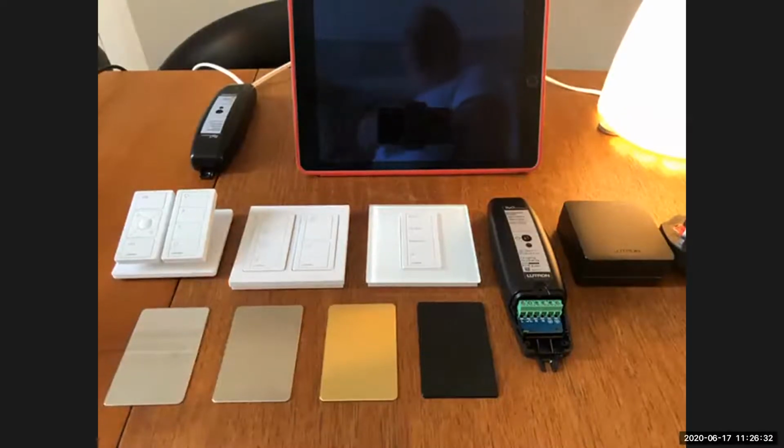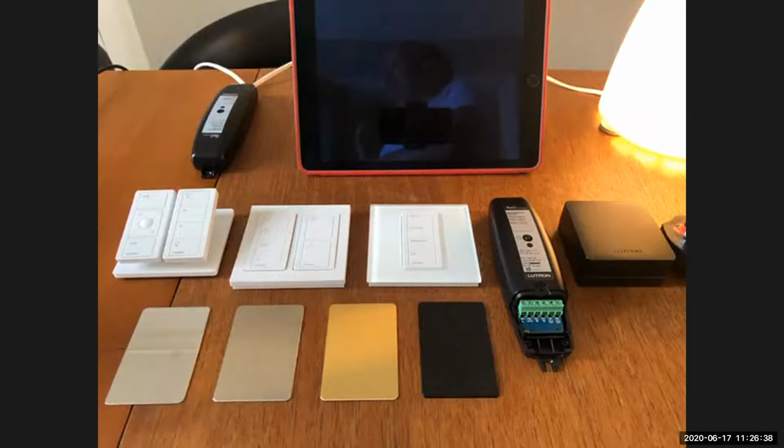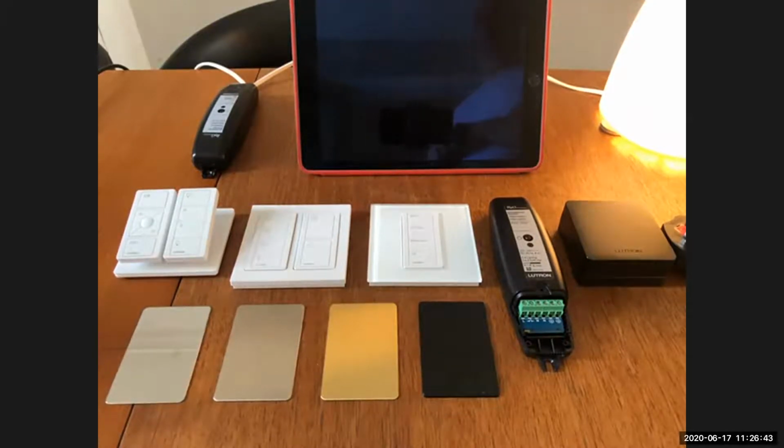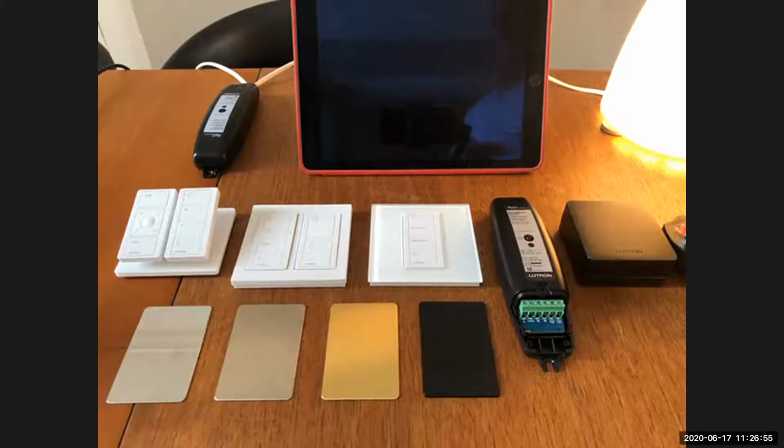So this is what we call leading edge dimming or trailing edge dimming. Our dimmer in this product is trailing, purpose built for LED. That forward phase or leading edge dimming can have a challenge. It can have what we call a latch load issue. And so with a 1 watt load, we kind of get ourselves all covered. So we don't need to have any issue there. That's its minimum. Normal dimming perhaps is 25, 30, perhaps even 40 watts. So it can be a challenge as well. But peace of mind and design resilience is what we're looking for. So you pick that product, it will dim it really well if it can be dimmed.